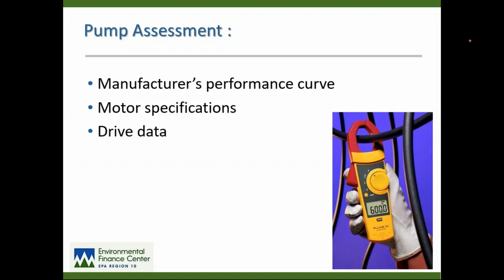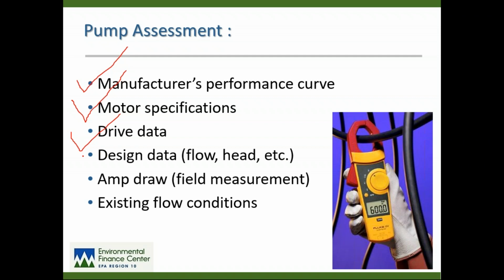So when you go and look at your pumps, you're going to be trying to find out some information. First, you want to get a hold of the manufacturer's performance curve for that pump, which most of the time should have been provided to you when the pump was purchased. You also want to have an idea of the motor specifications, and most of the time you can get that right off the motor nameplate that's attached to the motor. If the motor and pump are connected by some sort of drive or coupling, you want to find out what the information is on that. You'll already know what your design data is in terms of the gallons per minute that you need against the total dynamic head, and we'll talk about that term in a few more minutes.